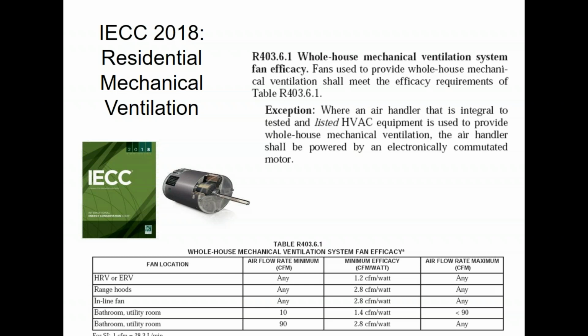If you're going to do that, you're probably doing that with an HRV or an ERV. And in our climate, you're going to want an ERV. HRVs would be further north, like more towards Canada. You might want to use an HRV there, but down here, you want an ERV, so you get the benefits of both the sensible and latent energy recovery or rejection. And we have to do a whole other separate webinar on how ERVs work. But an ERV would be one way to comply with this as well.